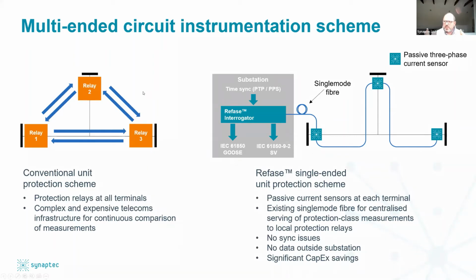We use this example because it's very typical of a transmission operator dealing with a queue of renewable grid connection requests at large scale. These are big industrial schemes, and the economic preference is to tee off an existing feeder to connect renewable generation sites like a big wind farm, rather than building new circuits, because whether you use pounds, dollars or euros, it's millions per kilometer to build new HV lines to these remote locations.